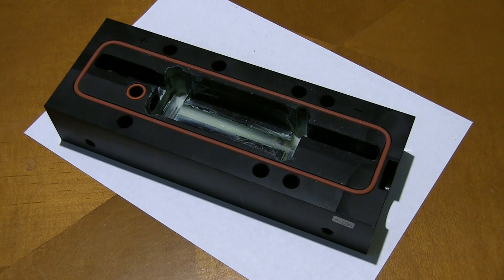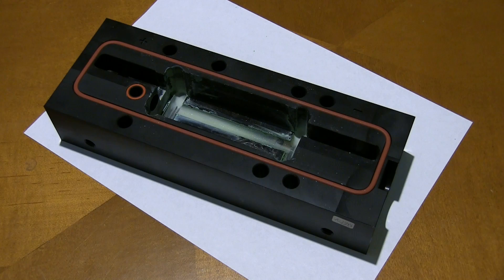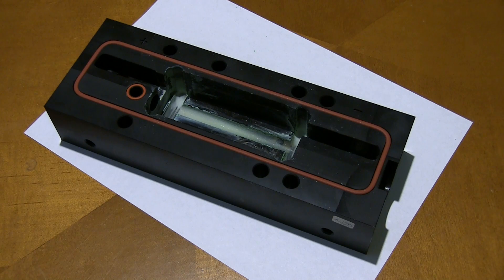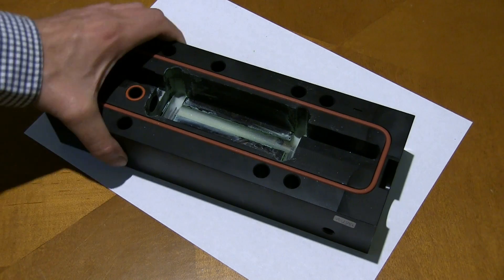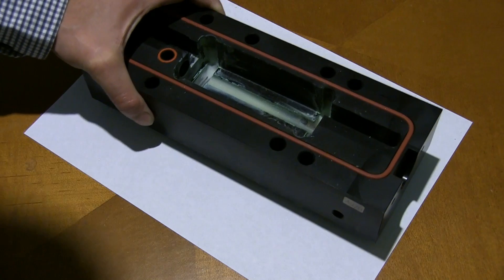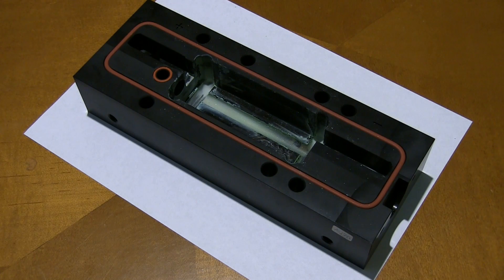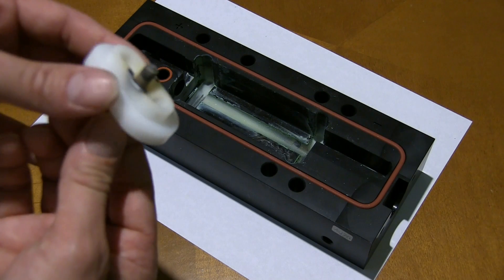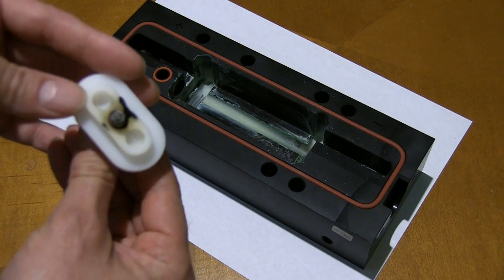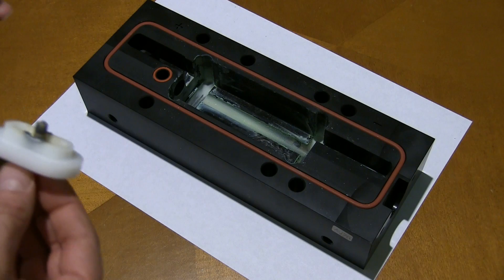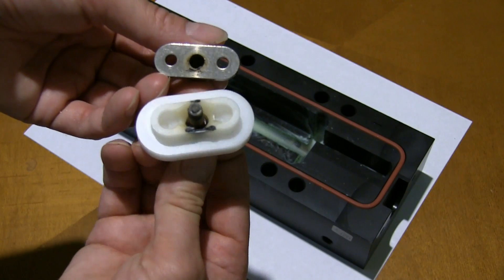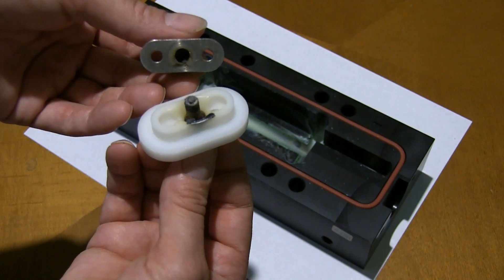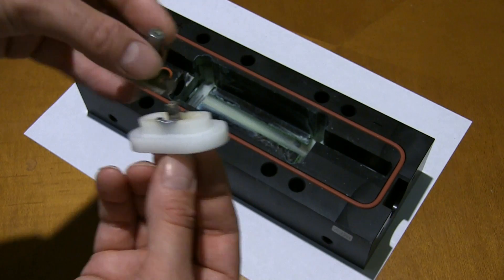This one seems quite an unusual design where the actual cavity and the rod and lamp are water cooled. Normally the cavity wouldn't be water cooled if there's a jacket around the lamp and the YAG rod, but this one it is as you can see, and it does look like we've had a bit of problem and there's some copper spewed out everywhere. And that seems to be from this lamp holder which has had a loose connection and that's been a disaster. I think that was in there, look, and now we've got copper contaminated the water system. That's most unfortunate.